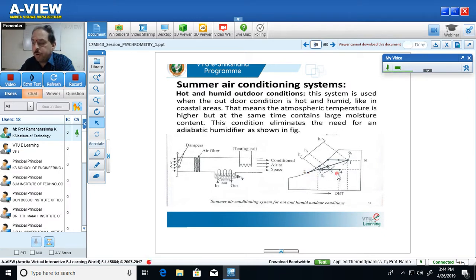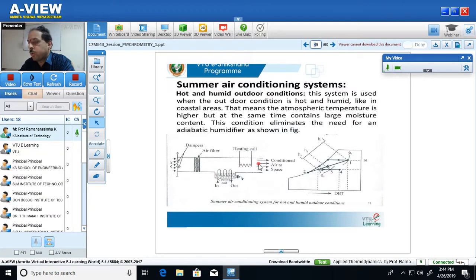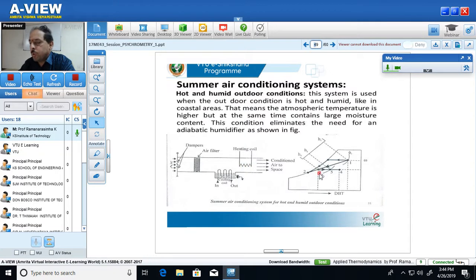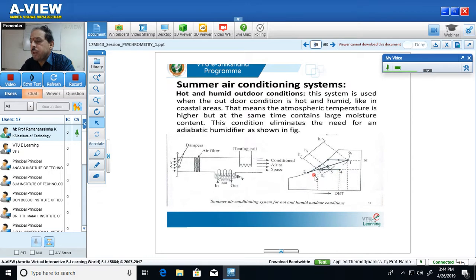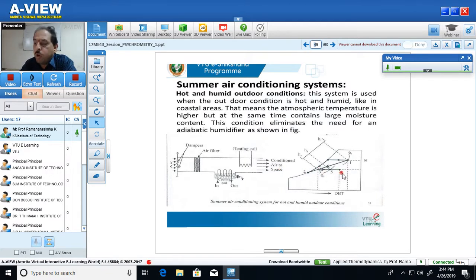When air passes through the heating coil, heating of air takes place. During this process, temperature of air increases and relative humidity decreases. This heating takes place at a constant specific humidity value, from point 3 to 4. Such a process is called the heating process. The air coming out of the heating coil — theoretically at point 4 — but in actual practice comes out at state point 5.